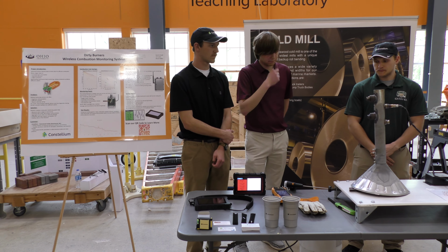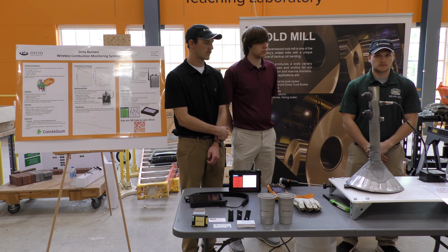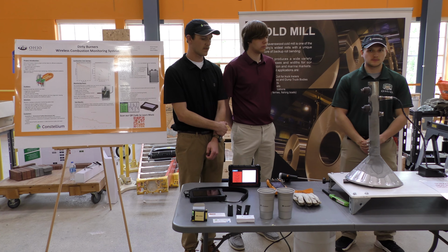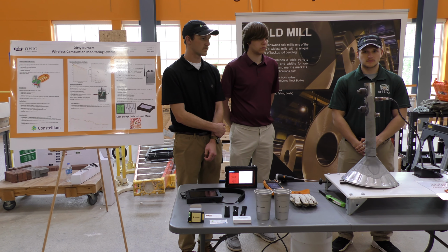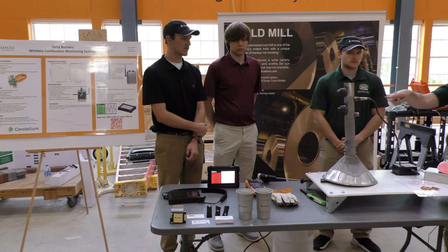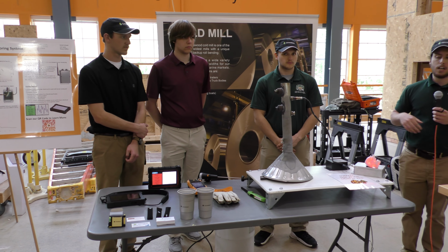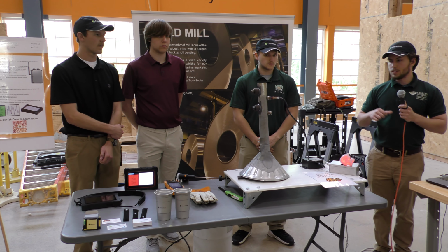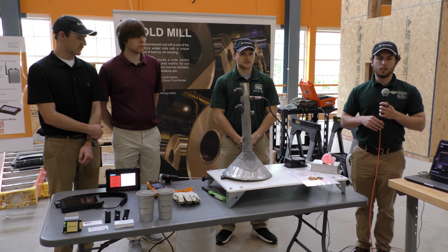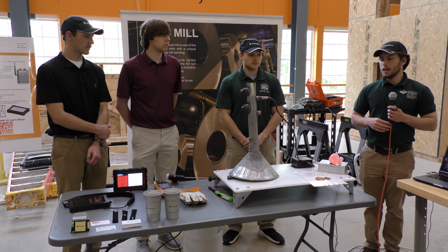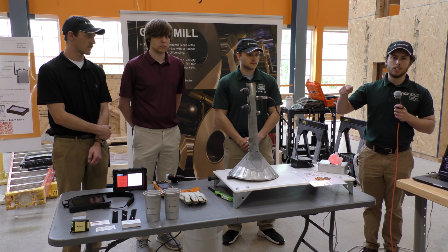So the way our system works is there's burners on these furnaces. There's 16 per furnace. Each one of those burners gets one module that we've made, which right here you can see. And those modules can control a sensor that actually monitors the oxygen levels. This data is collected by us, and we send it over to a plant network so they can have a log of their data, and we also send it to a tuning device so they can tune the air-fuel ratio in real time.